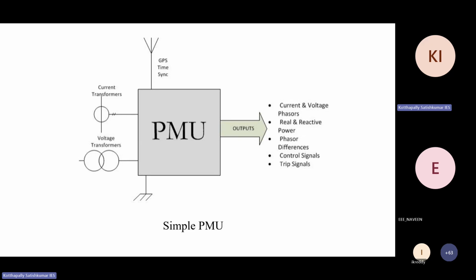Now in simple terms, I can show this PMU. You give inputs from the current transformer and the voltage transformer - three-phase currents R, Y, B and voltages R, Y, B as inputs. Since currents are in hundreds or thousands, you use a CT, which gives a 1 amp or 5 amp reading. Similarly for voltage, you use PTs, taking measurements from the PTs and giving that input to the PMU. So the PMU has inputs of current, voltage, and GPS, and its output is current and voltage phasors.